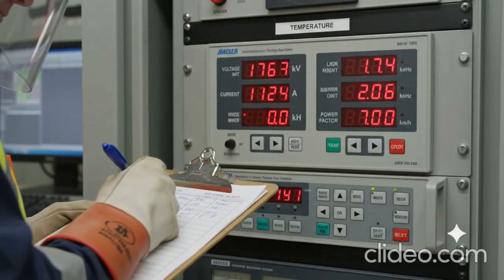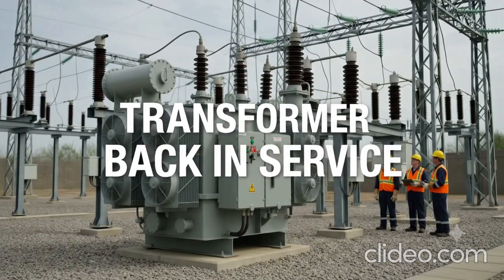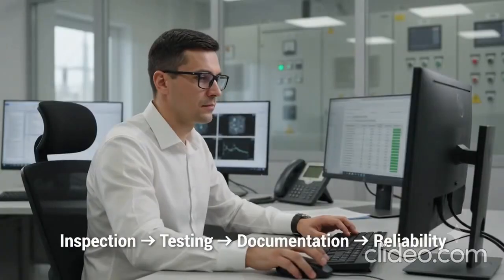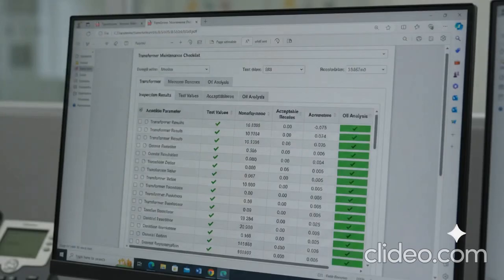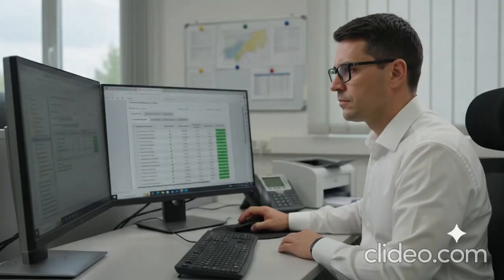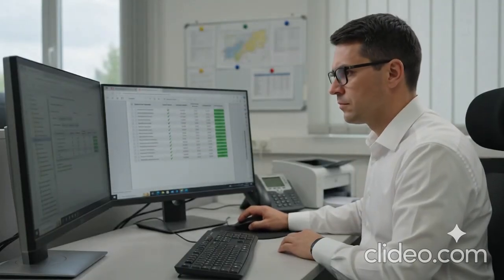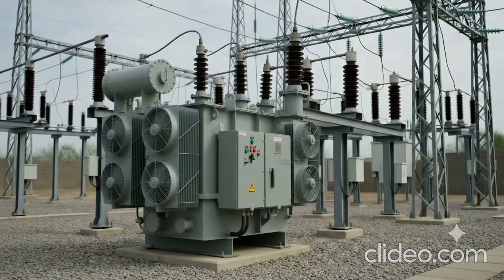Any abnormal noise or indication is investigated immediately. Oil leakage is also checked. Finally, all inspection findings, test results, observations, and corrective actions are recorded in the transformer maintenance report. Proper documentation helps establish a reliable record.